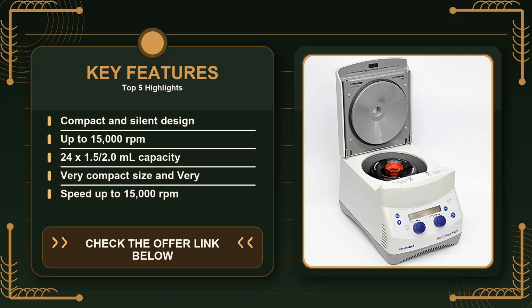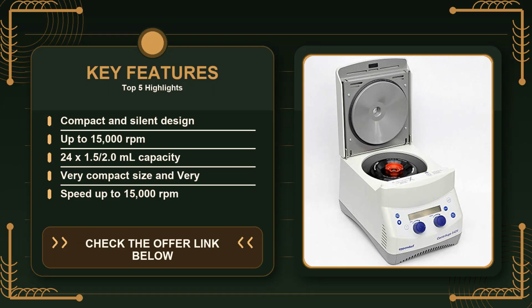Let's talk about the rotor itself. The FA452411 holds 24 microcentrifuge tubes, each either 1.5 milliliters or 2 milliliters. That capacity is perfect for batch processing. A typical plasmid prep might need you to spin 12 tubes, and you have room to double up without having to reload. The design is also fairly forgiving. The tube slots are wide enough that you don't have to fuss over perfect alignment, yet tight enough to keep the tubes from wobbling during acceleration.